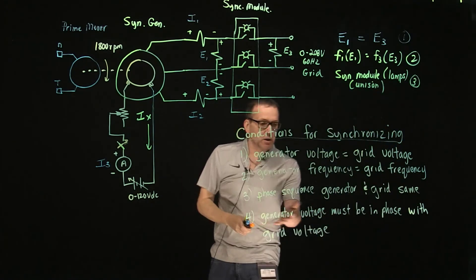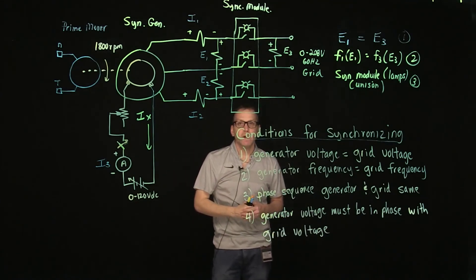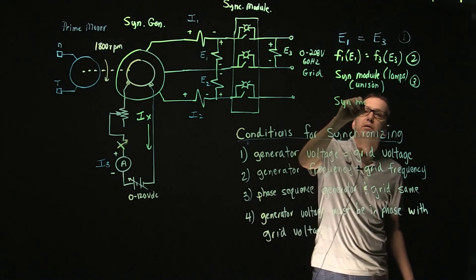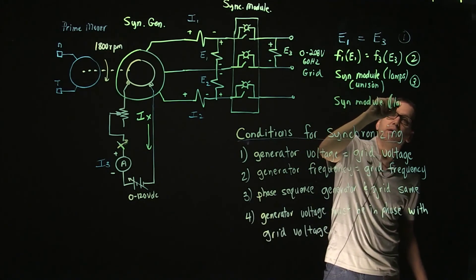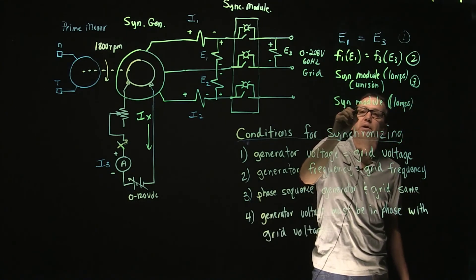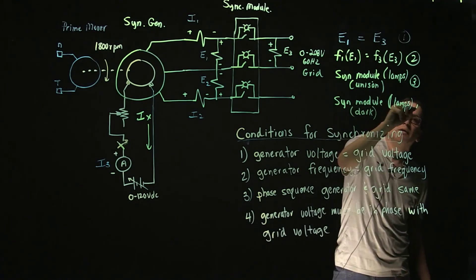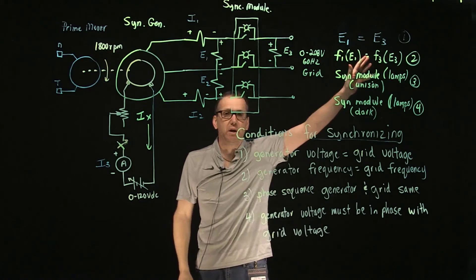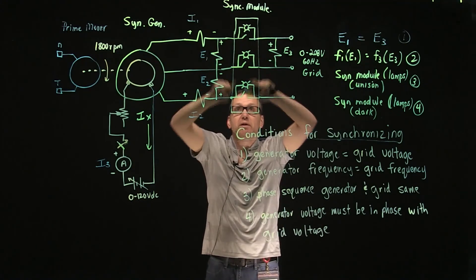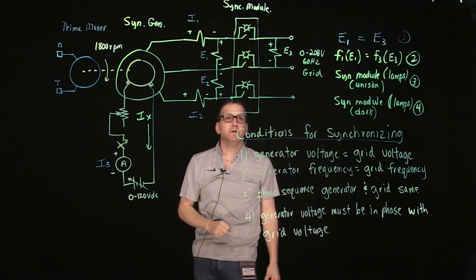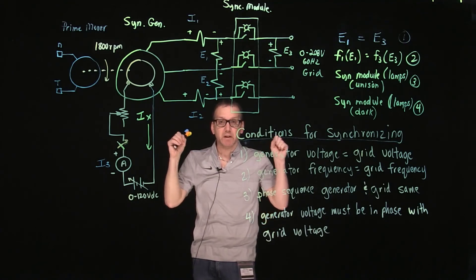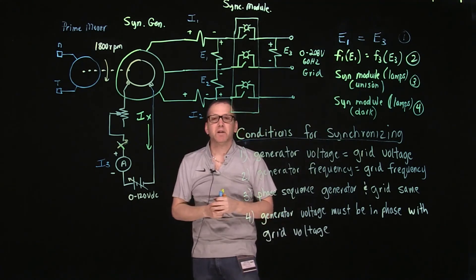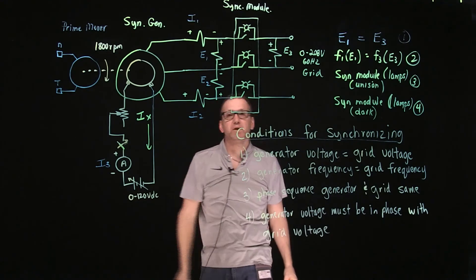For condition number four, the generator voltage must be in phase with the grid voltage. We can also determine this using the synchronizing module lamps, except now we are looking at when the lamps are dark. When the lamps are dark, the two voltages are in phase, there is zero volts across the switch, and we can close the switch to synchronize the two systems. You should see a nice slow beat frequency, voltages should be equal, generator frequency slightly higher, and when the lamps are dark, close the switch on the synchronizing module.